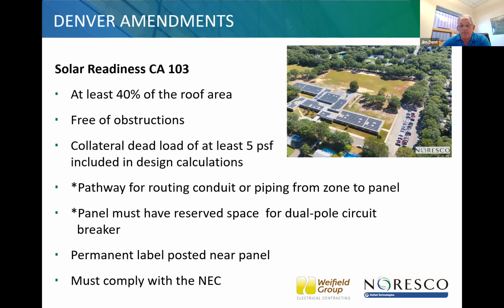Interestingly enough, Denver does not require you to have busing capable of supporting both the utility feed and the photovoltaic feed. So when we built the research support facility back in 2008, 2009, we had a 4,000 amp feed coming from the utility and a 2,000 amp photovoltaic array on the roof. So we had to have a 6,000 amp switchgear.